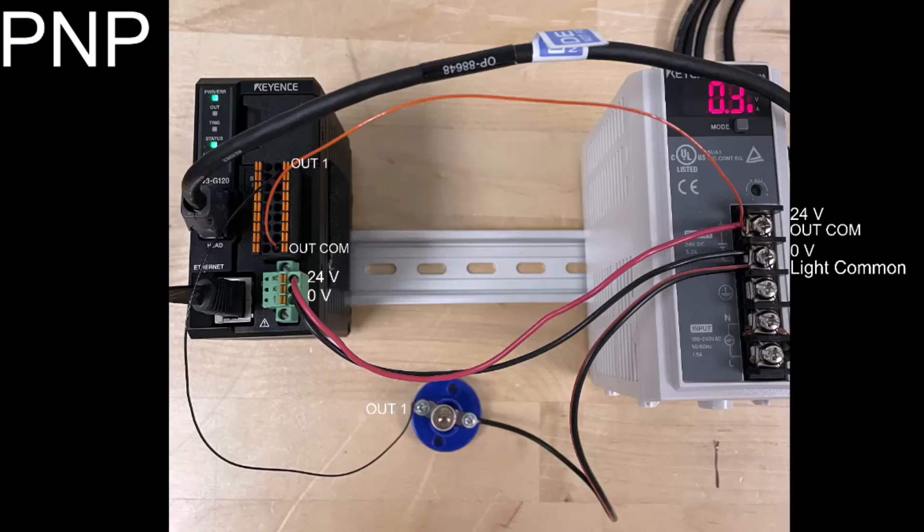I'm using a black wire to connect that to my light, and then I have an orange wire connected to terminal 18 for my output common. And because I have a PNP setup, my output common is connected to my 24-volt side of the power supply.